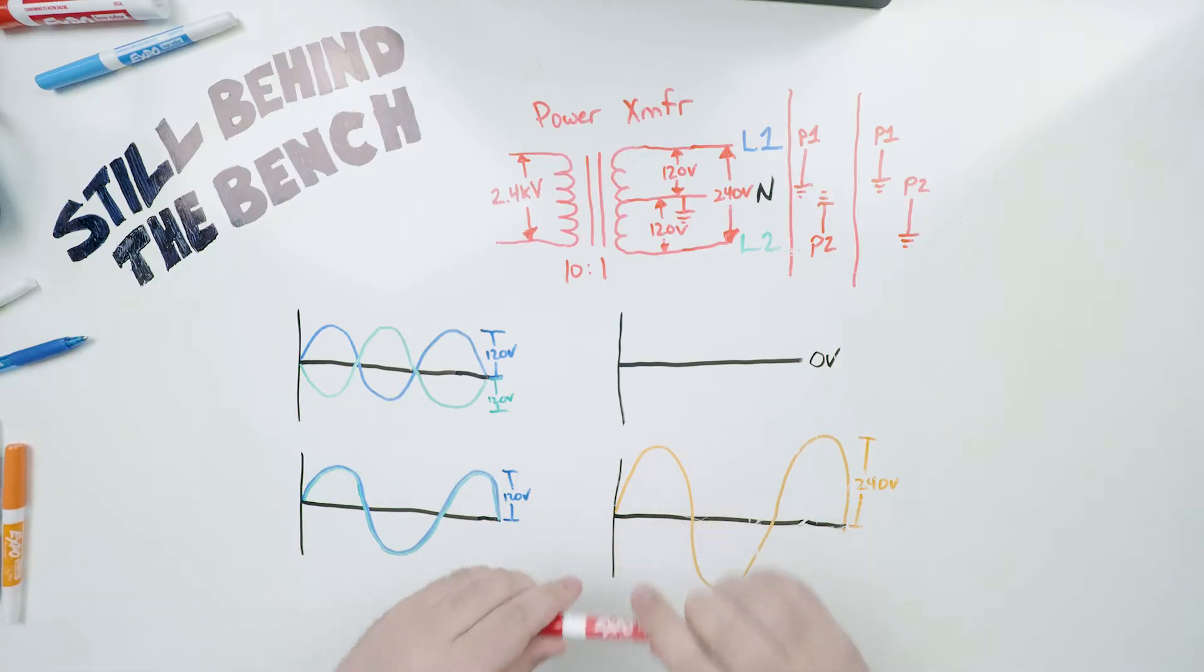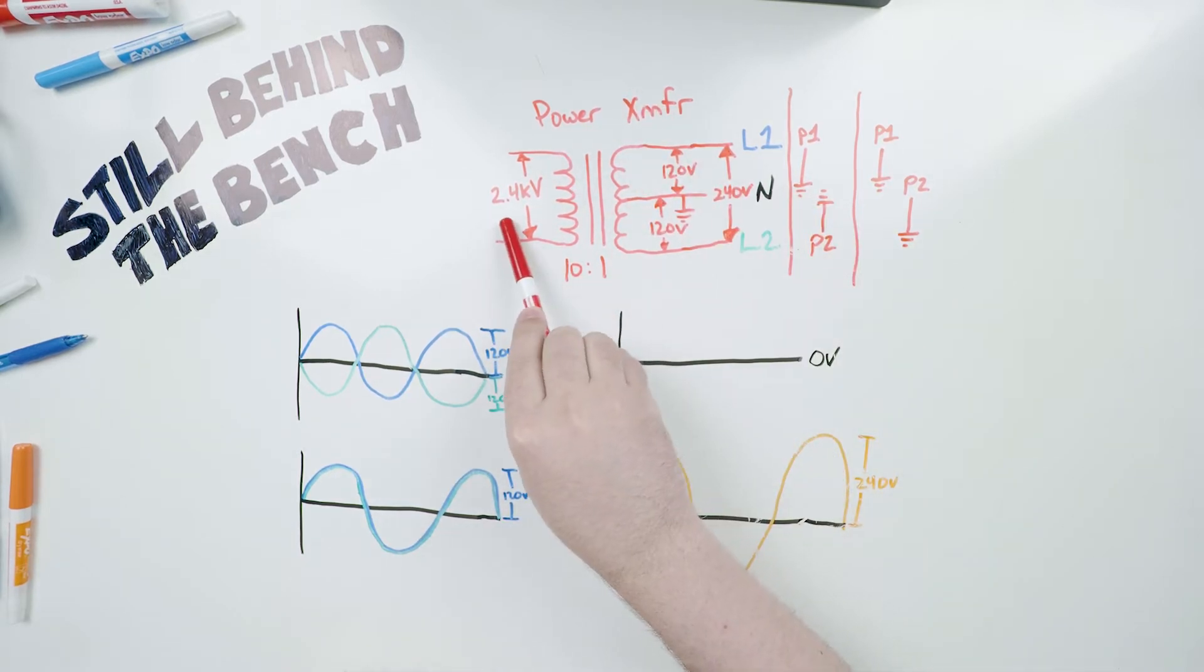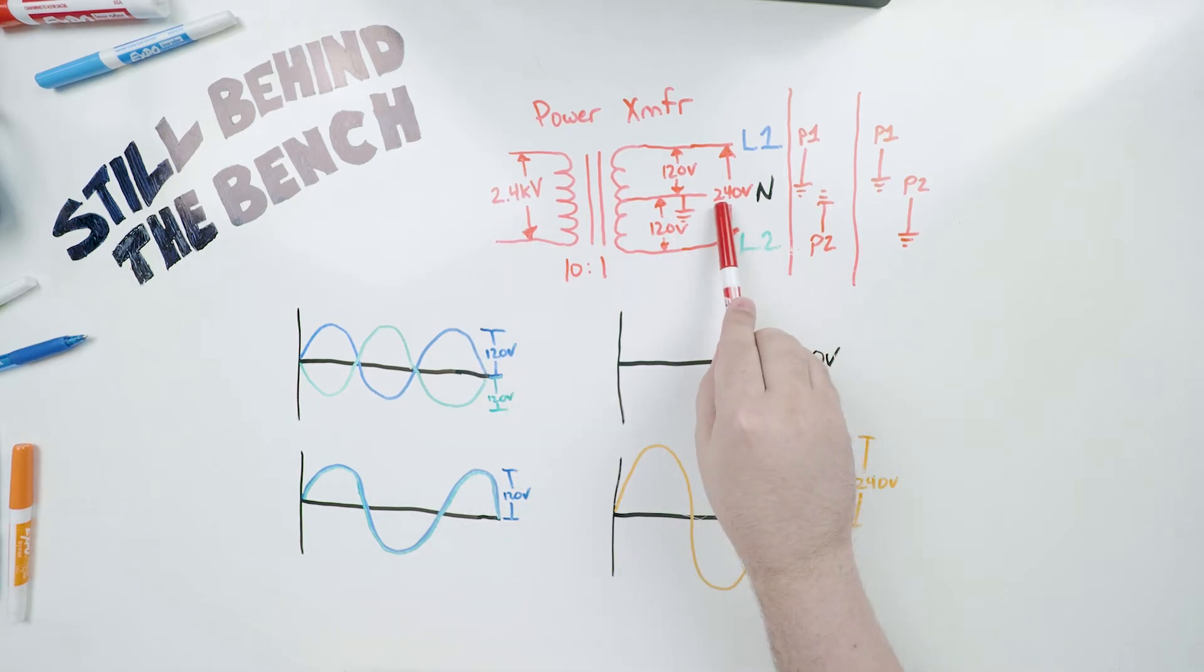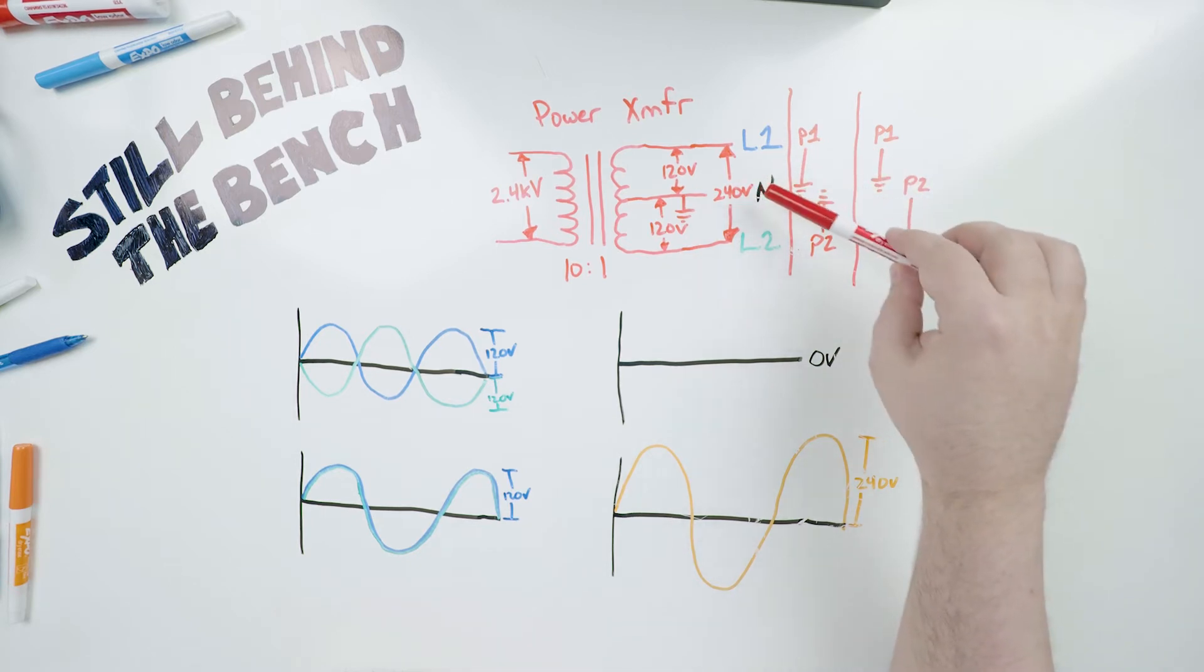Now to further explain this, we'll go to the board and I can show you some diagrams. Alright. So here we are at the bench talking about split phase power. So we have our power transformer, the 10 to 1 ratio. It has a 2.4 kilovolt input and a 240 volt output. It also has the center tap where there is a voltage potential of 120 volts between line one and neutral. And there's 120 volts between line two and neutral. Now, if you were to connect an oscilloscope to line one and line two, attaching the grounding straps for each probe to neutral, you'd see a waveform that looks like this.